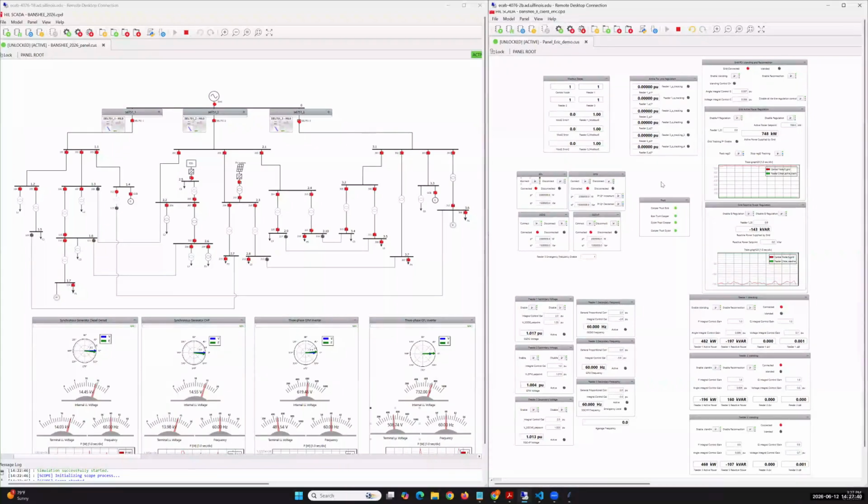So the first thing that we need to do is drive the active and reactive power flow here to 0 by enabling islanding. And we can see here that all of the nodes are currently trusted. So I'm going to start this. And the distributed controls, we are being sent set points and all 3 nodes are trusted. And we are now waiting for the system to island.